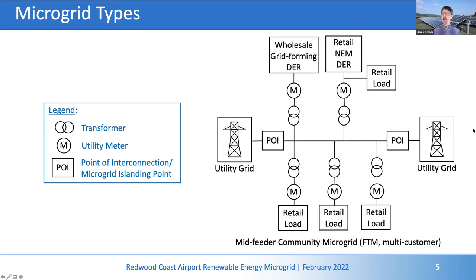The next case is a bit more complicated again. Depending on where you need the resilience and where you have the ability to put in solar and batteries, that determines where you're located on the grid. There could be more points of isolation, but in this case, for the same diagram as before, I'm showing two points of isolation. This is a mid-feeder community microgrid, and now you have two points of isolation, which complicates the controls and protection, in particular the transitions.